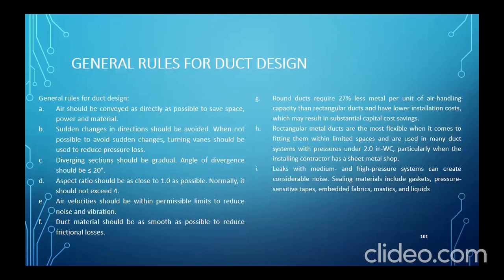Next, general rules for duct design. A, air should be conveyed as directly as possible to save space, power, and material. B, sudden changes in direction should be avoided. When it is not possible to avoid sudden changes, turning vanes should be used to reduce pressure loss. C, diverging sections should be gradual. The angle of divergence should be less than or equal to 20 degrees. D, aspect ratio should be as close to 1.0 as possible. Normally, it should not exceed 4.